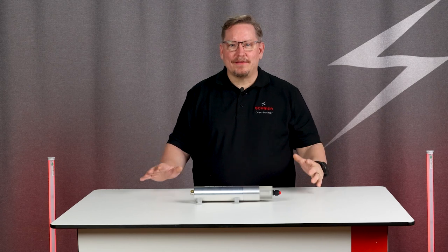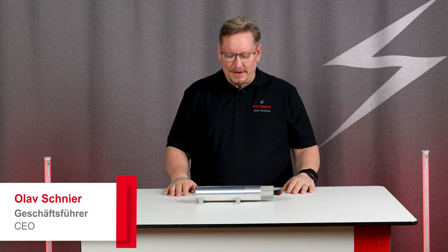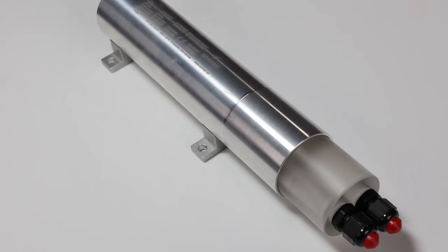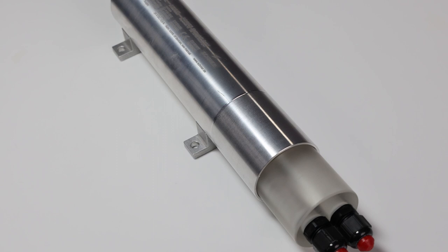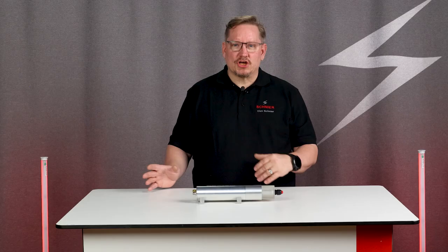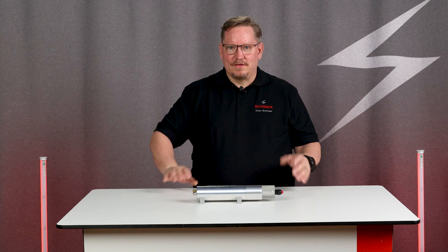When does it make sense to install a discharger? This is exactly the question we are often asked, and I would like to answer it in this video. First of all, what is our discharger? Our discharger is a system that can discharge the high voltage within a very short time, and, unlike a grounding switch, works completely electronically without sparks. We control it with 24 volts.